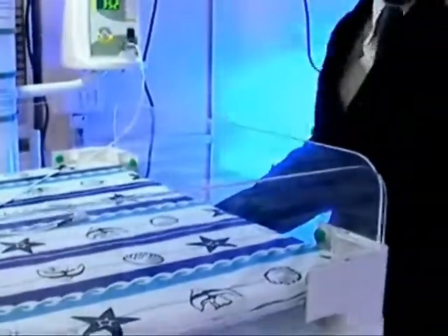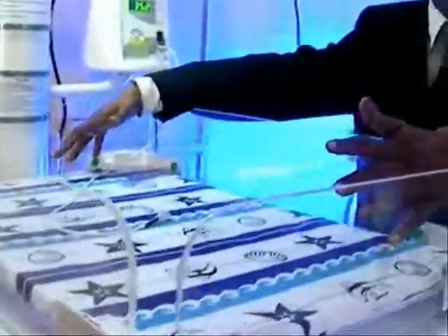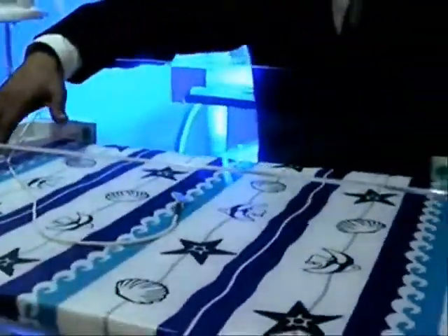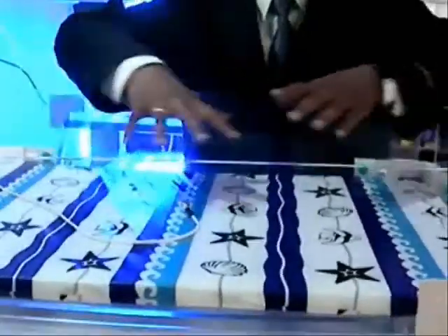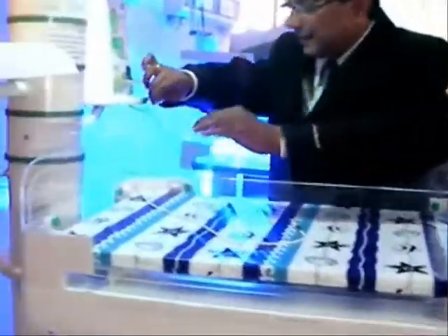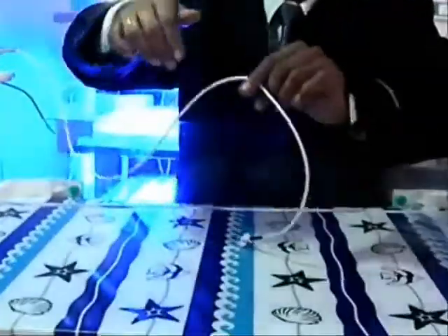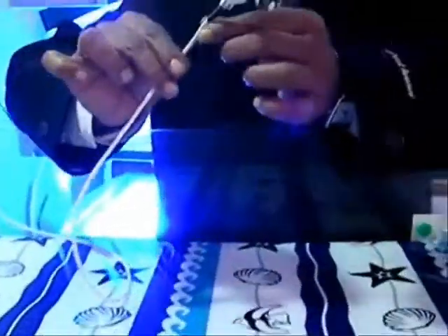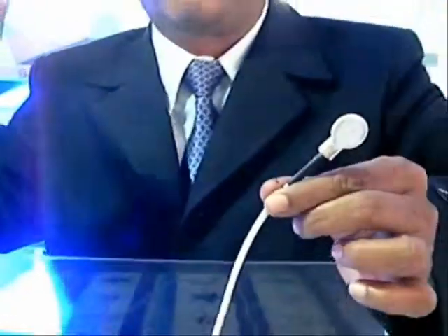Now, coming to the baby area, it's a large, soft cushion baby area where the baby can be comfortably placed. This is the sensing device that senses the baby's body temperature. It's a specially made skin temperature probe. And mind you, it's not disposable, it's reusable. It has a 4-core cable inside it, that's why it's very tough.